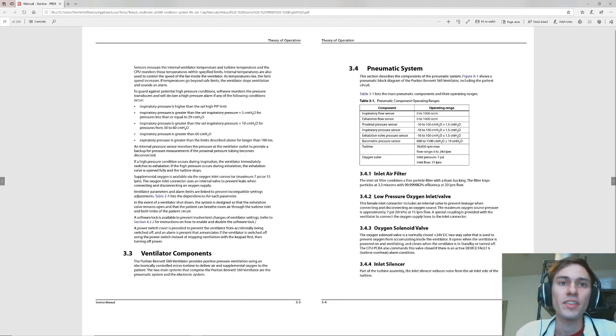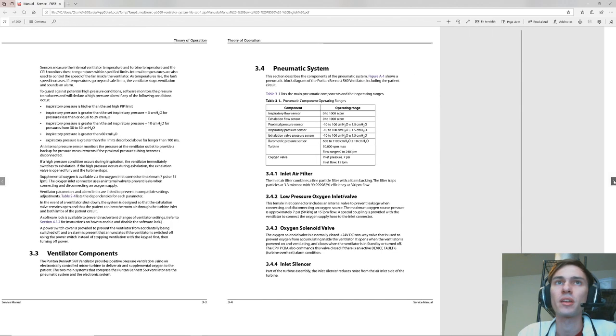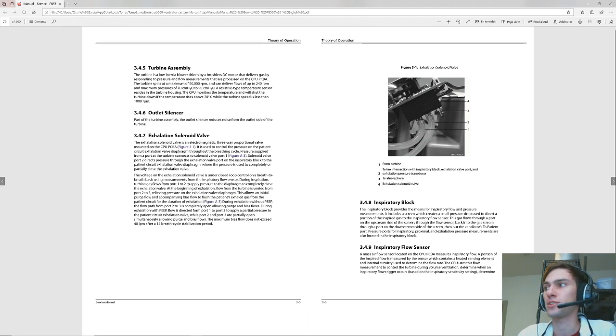Okay. Let's see, the inlet silencer, there's a turbine assembly. An inlet silencer removes noise from the air inlet side of the turbine. I guess that's like an important quality of life feature. It would really suck to be stuck in a hospital and all you could hear is these like things everywhere. Outlet silencer, exhaust, exhalation solenoid valve. The exhalation solenoid valve is an electromagnetic three-way proportional valve. Oh, okay, so I was right. It is a three-way valve. Pressure supplied from a port at the turbine connects to solenoid valve 1. Solenoid valve port 2, pressure through the exhalation valve port on the inspiratory block to the patient circuit exhalation valve diaphragm, where the patient is...